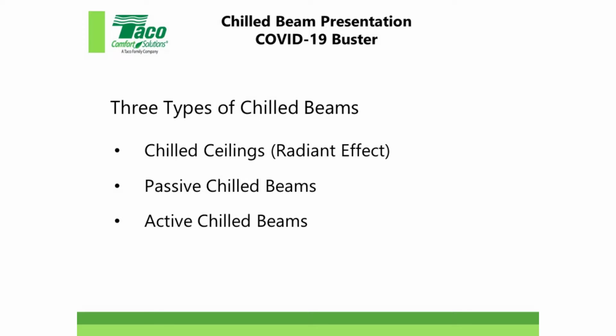Then you have passive chill beams. I'm going to show you some pictures of those. Those are just for cooling. There's no air induced into that. And probably most projects nowadays have what they call active chill beams. I'm going to show you some pictures, but that's a system where the primary air is induced or brought into the chill beam, the dry primary air.